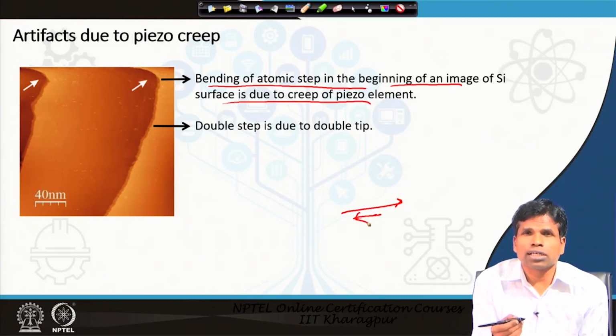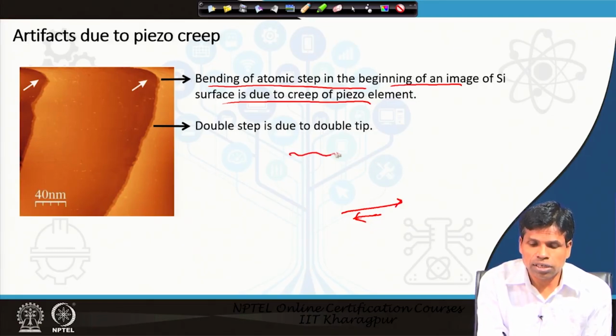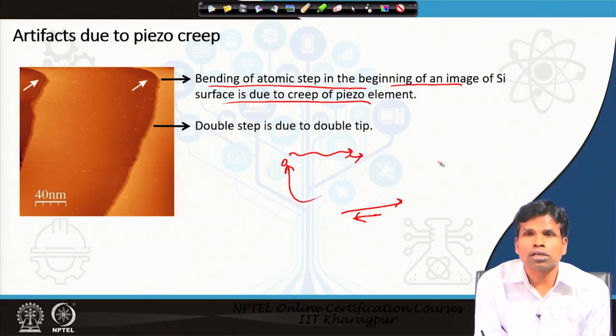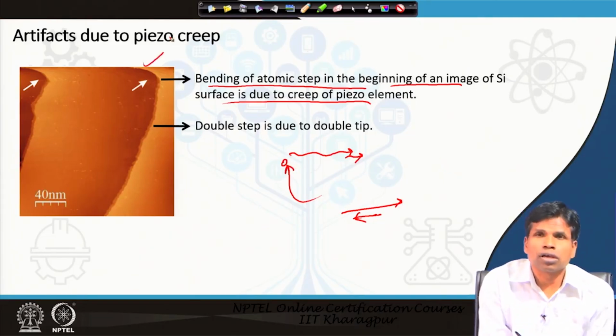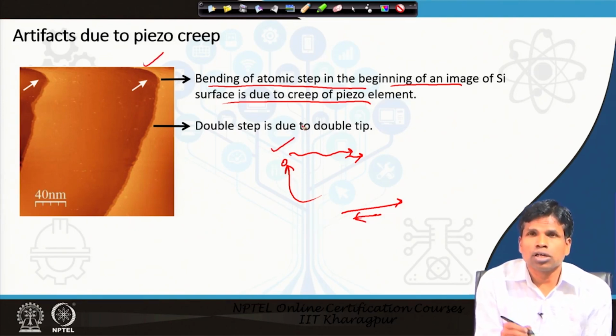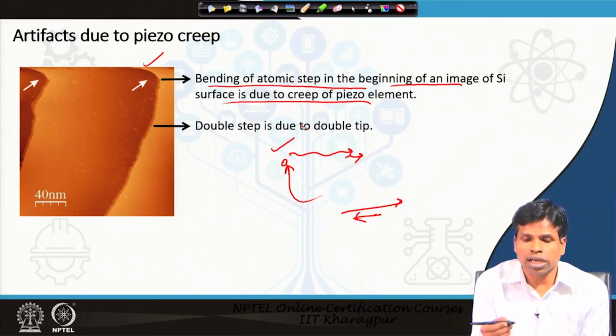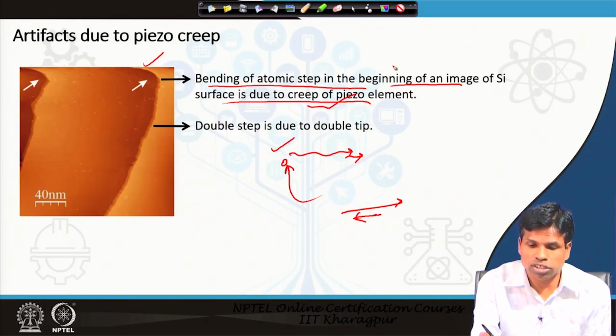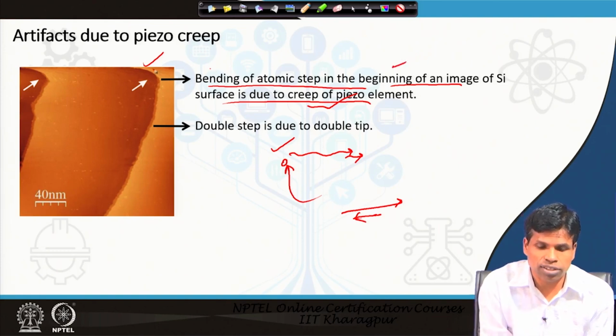It never acts instantaneously. It takes time. It is a time dependent phenomenon. So by the time our voltage has come back to the original position, the tip is still moving in the other direction, and that leads to this bending. So the piezoelectric scanner does not react instantaneously but takes time, and that leads to creep or distortion of the image, and in these cases bending is occurring.